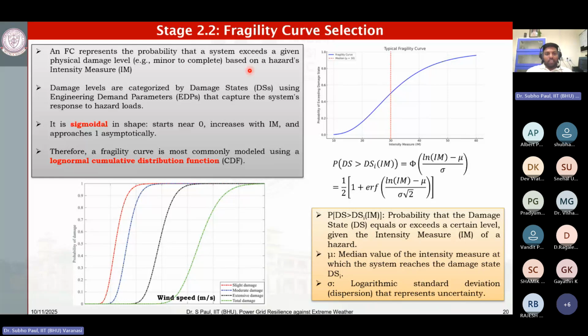This is what I mentioned - your fragility curve is designed for damage states. For a pole, the first damage state is displacement, that is whether your pole has been tilted or not. The second damage can be that, since the lines are at the tip of the pole, if that tip has broken, you can say the pole is not working - it's still standing at 90 degrees, but the tip has broken, or an insulator at the tip has broken, so now you cannot operate with that pole.